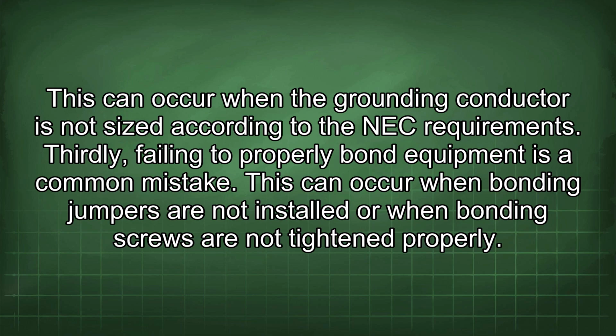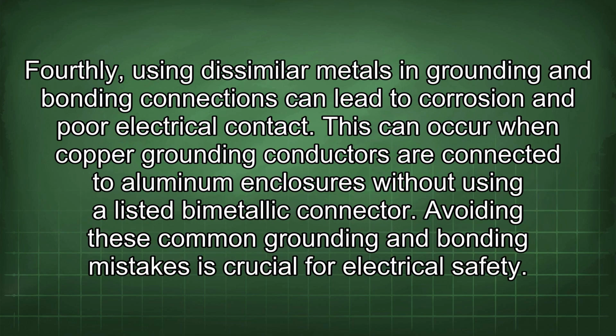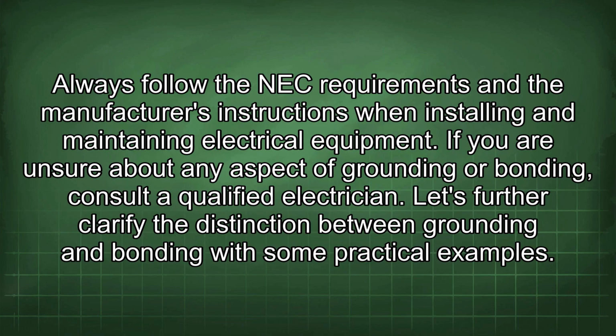This can occur when bonding jumpers are not installed or when bonding screws are not tightened properly. Fourthly, using dissimilar metals in grounding and bonding connections can lead to corrosion and poor electrical contact. This can occur when copper grounding conductors are connected to aluminum enclosures without using a listed bimetallic connector. Avoiding these common grounding and bonding mistakes is crucial for electrical safety. Always follow the NEC requirements and the manufacturer's instructions when installing and maintaining electrical equipment. If you are unsure about any aspect of grounding or bonding, consult a qualified electrician.